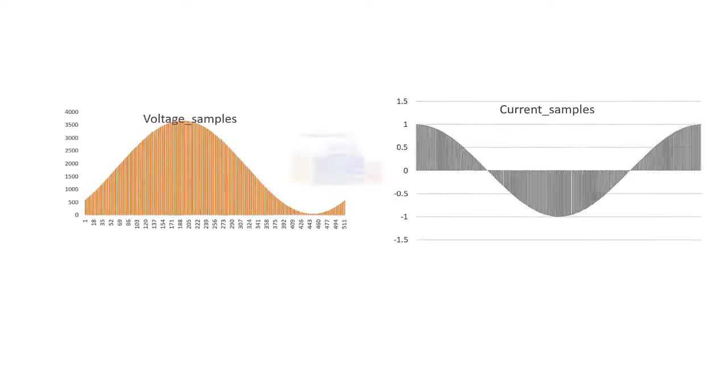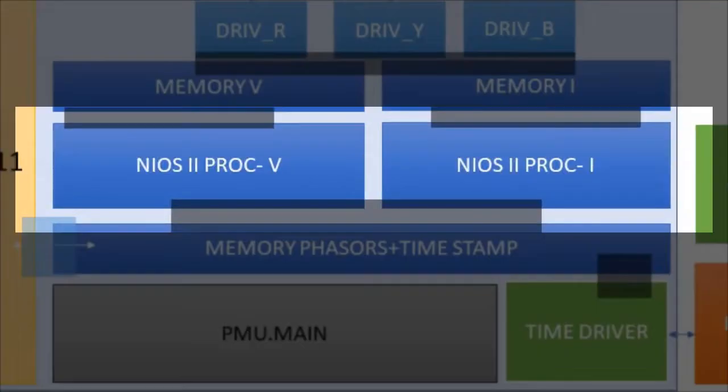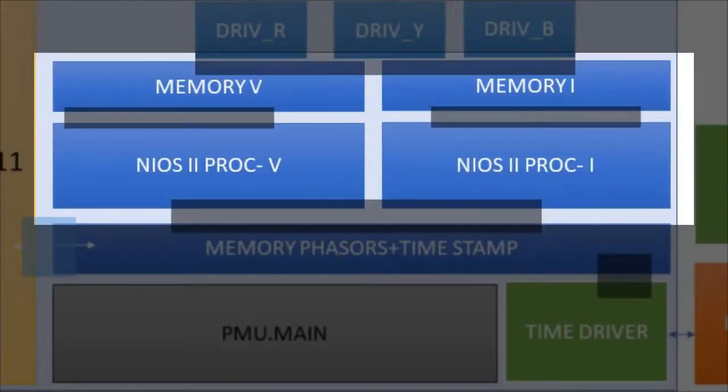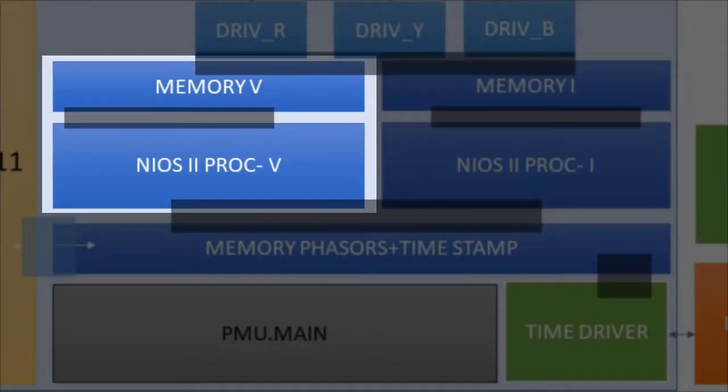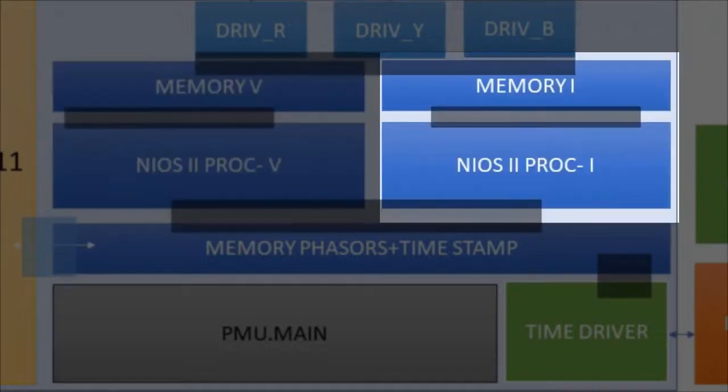When memory is filled with 256 digital samples of half-cycle waveform, the phasor processing cores are invoked to collect the digital samples from memory and apply phasor estimation technique. The voltage processing core acts on voltage samples of three-phase voltage waveform and current processing core acts on current samples of three-phase current waveform.